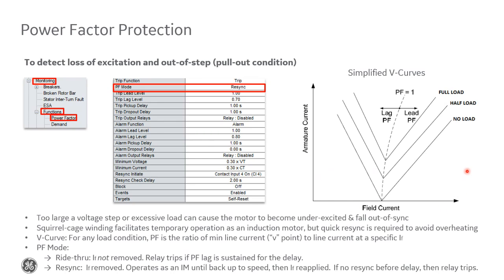And this is just a plot of the stator current versus the field excitation for different load levels. So here we're showing no load, half load, and full load. The minimum stator current for each load level is that unity power factor, which is this bottom point for each curve. Now, if you decrease the field excitation, the stator current will increase and the power factor will become lagging. So this area is the lagging power factor.